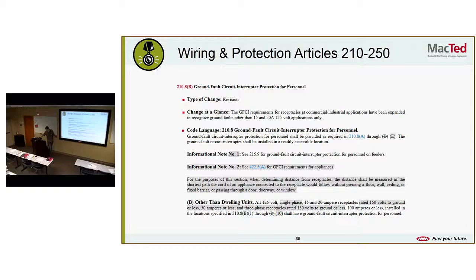So this says GFI protection shall be provided as required in 210.8(A). Needs to be installed in a readily accessible location. So everybody know what we're talking about, the little GFIs with the reset and the test button, stuff like that. Those have to be installed in a readily accessible location. And for the purposes of this section, when determining distance from receptacles, the distance shall be measured as the shortest path the cord of an appliance connected to the receptacle would follow, without piercing a floor, wall, ceiling, or fixed barrier or passing through a door, doorway, or window.